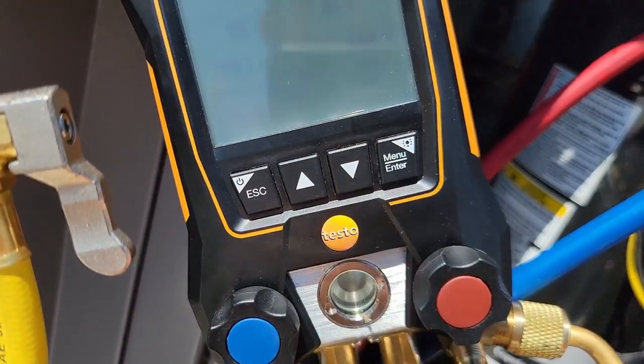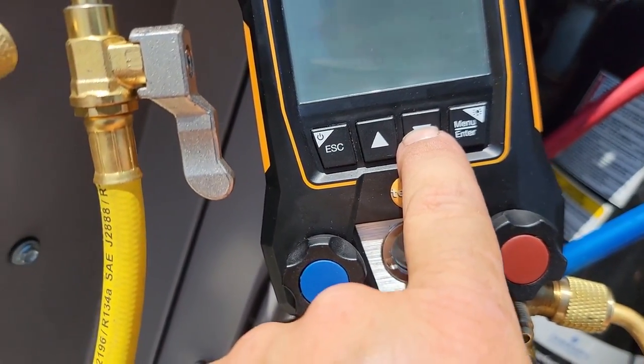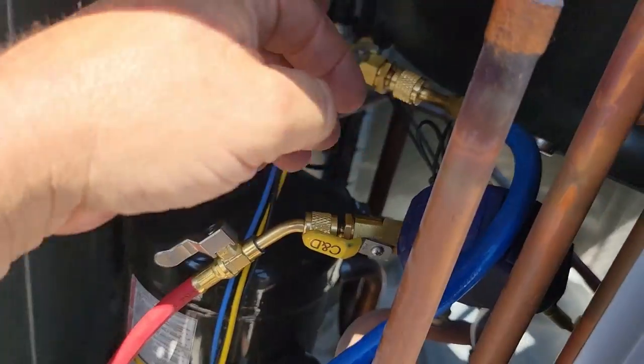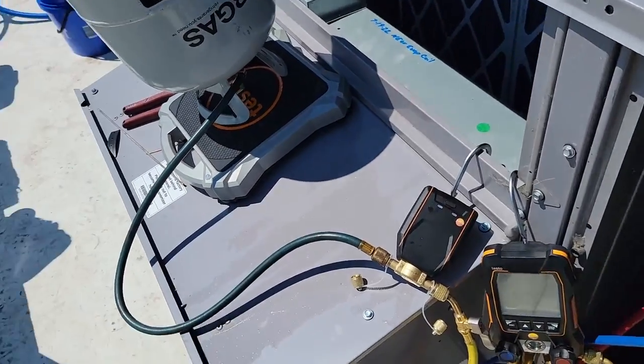So we've got 8.2 in there, we got 0 there, and there's a start button right there you couldn't see. Hit start. There it goes. Open up our valve. Weight is going in. It did a little bit and it stopped. Let's go ahead and remove our micron gauge. So you just brought in some more again. Slowly adding it in spurts.